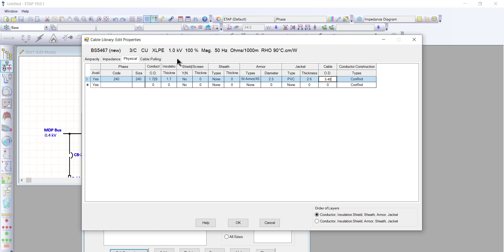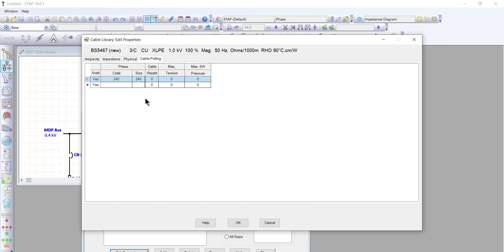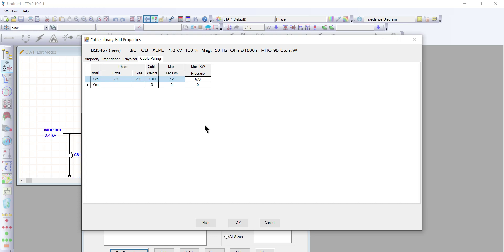Now let's go to the last section of the cable library: cable pulling. The weight of the cable per 1,000 meters is approximately 7,100 kg. The maximum tension is 7.2. The pressure is 670. We have completed everything — ampacity, impedance, physical, and cable pulling parameters.